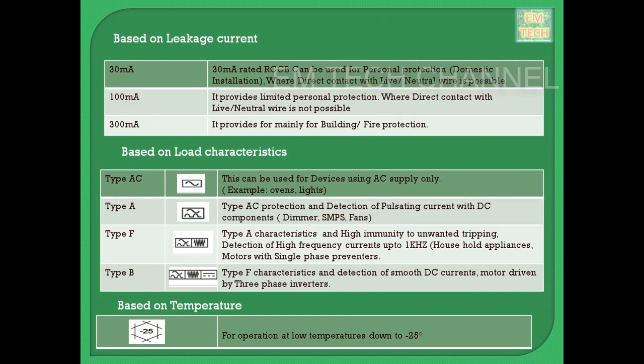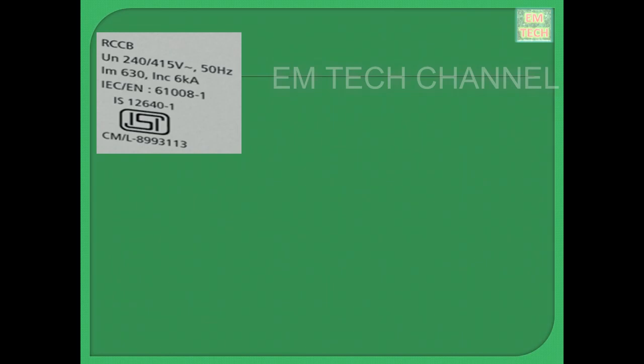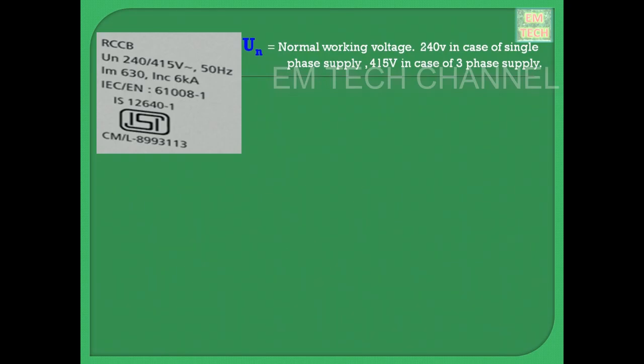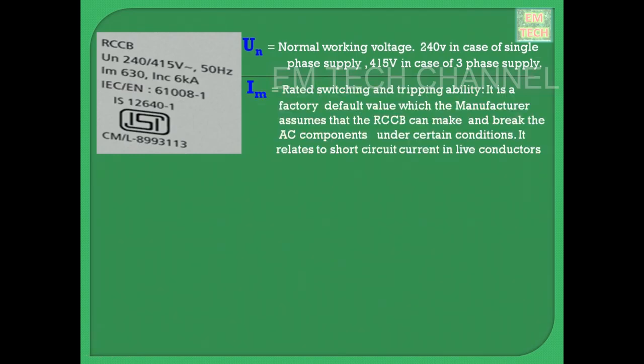Hope you understood the factors to be considered before selecting the RCCB. Let's see the parameters of RCCB. In this, you can see UN. UN means normal working voltage. It is 240 volt in case of a single phase supply and 415 volt in case of three phase supply. Next, what is IM? IM means it is the rated switching and tripping ability, and it is a manufacturer's set value. The manufacturer assumes that the RCCB can make and break the AC supply under specified conditions. This value of current that the RCCB can make and break relates to short circuit current in live conductors.